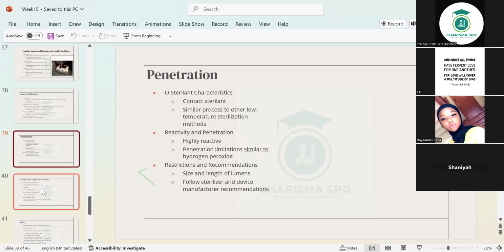Ozone sterilant characteristics, contact sterilant. Okay, similar process to other low temperature sterilization methods. Reactivity and penetration, highly reactive. Penetration limitations similar to hydrogen peroxide.